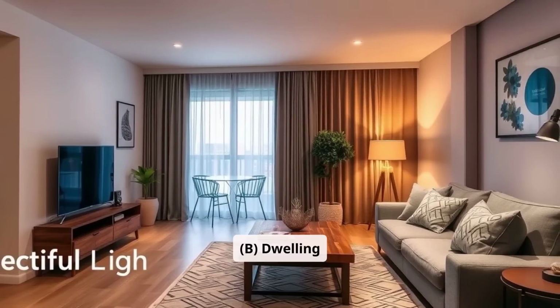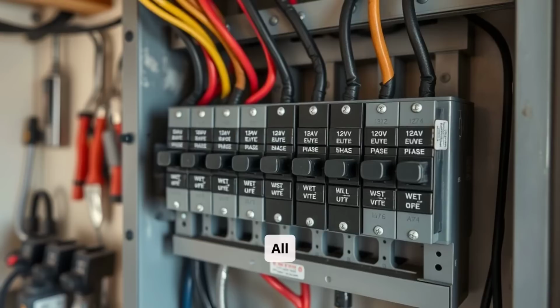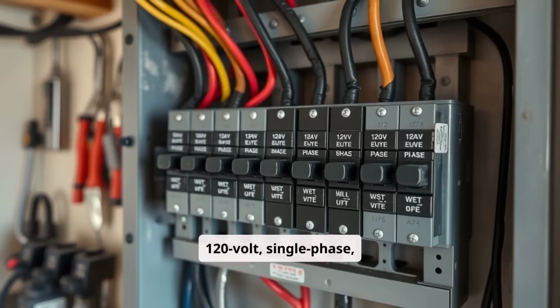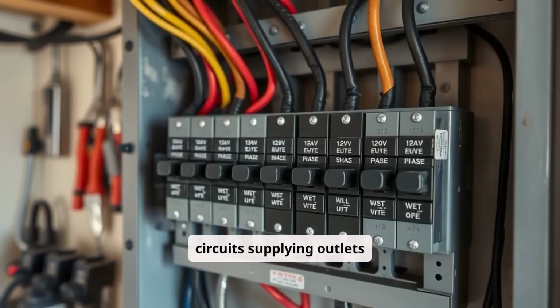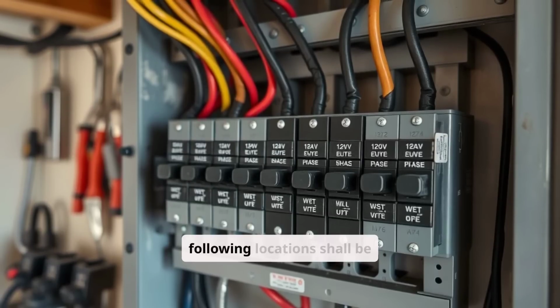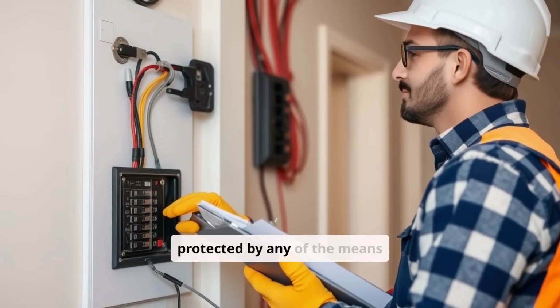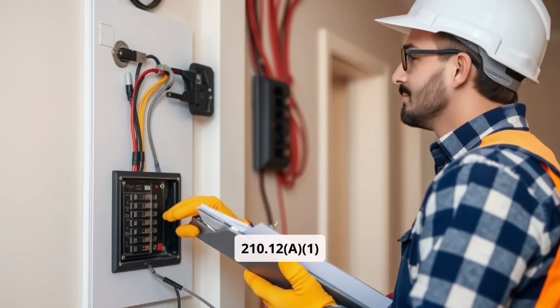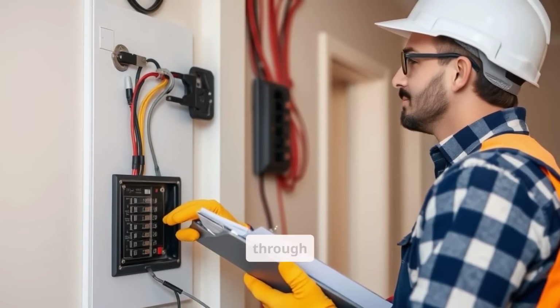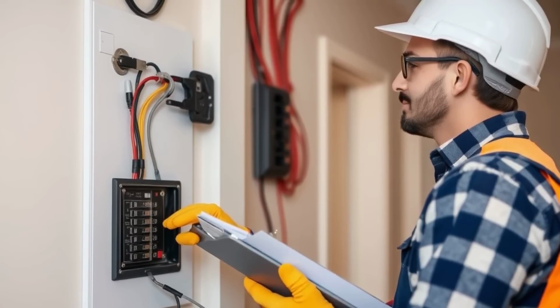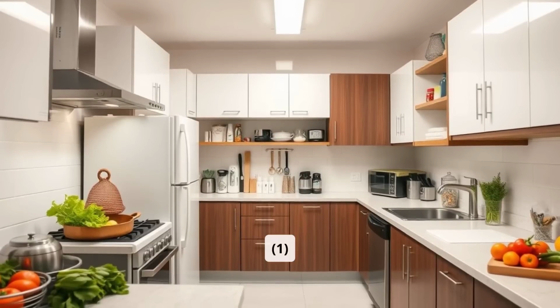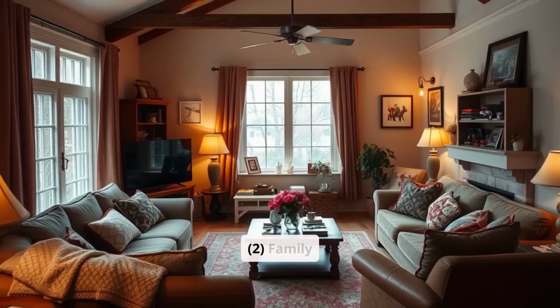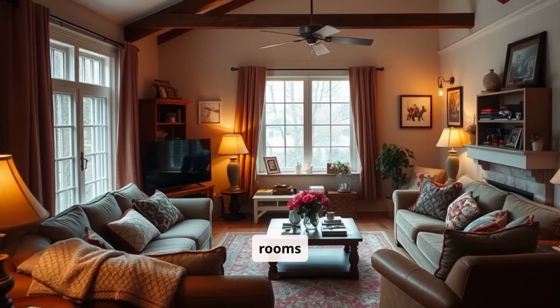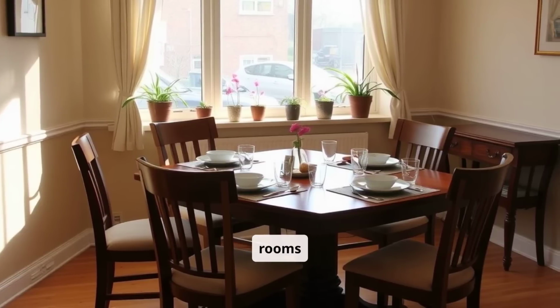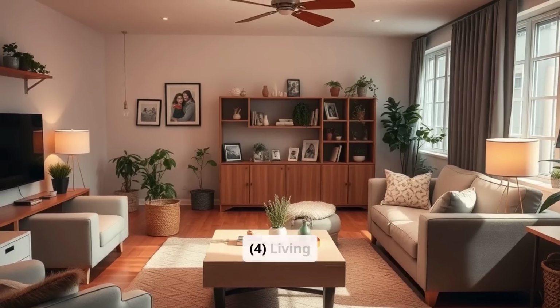B. Dwelling units. All 120 volt, single phase, 10, 15, and 20 ampere branch circuits supplying outlets or devices installed in the following locations shall be protected by any of the means described in 210.12(A)(1) through (A)(6). 1. Kitchens. 2. Family rooms. 3. Dining rooms. 4. Living rooms.